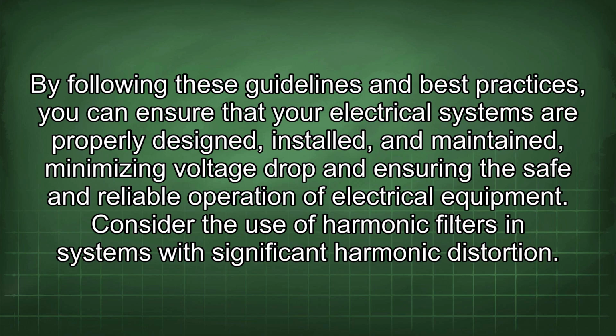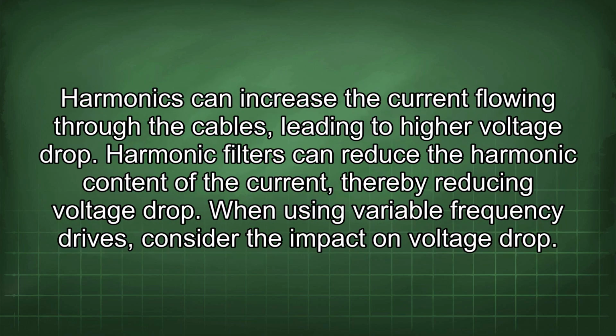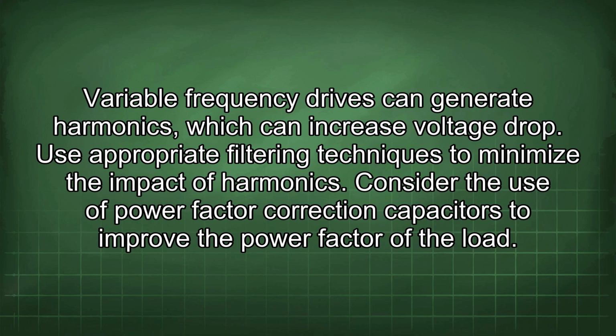Consider the use of harmonic filters in systems with significant harmonic distortion. Harmonics can increase the current flowing through the cables, leading to higher voltage drop. Harmonic filters can reduce the harmonic content of the current, thereby reducing voltage drop. When using variable frequency drives, consider the impact on voltage drop. Variable frequency drives can generate harmonics, which can increase voltage drop. Use appropriate filtering techniques to minimize the impact of harmonics.